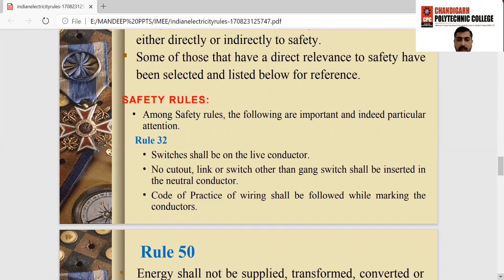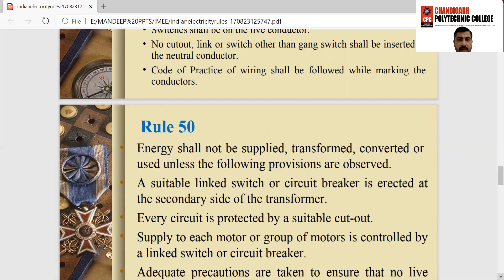Under Rule 50, energy shall not be supplied, transformed, converted, or used unless the following provisions are observed. These are the basic instructions for the safe use of electricity. A suitable linked switch or circuit breaker is erected at the secondary side of the transformer. Every circuit is protected by a suitable cutout.